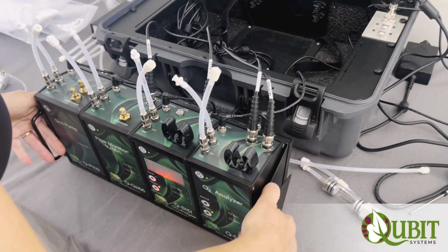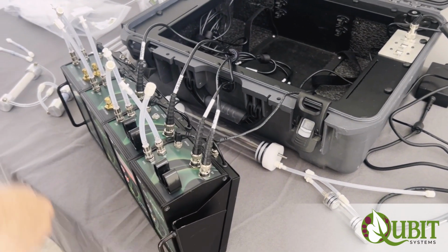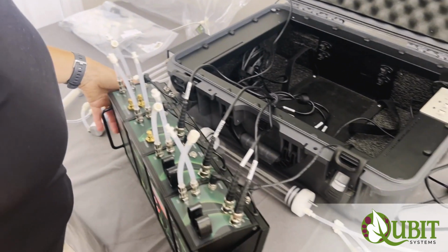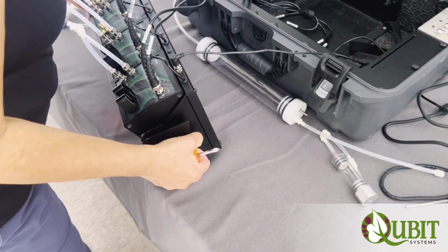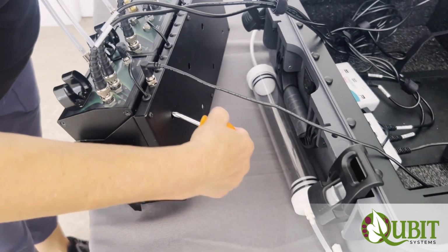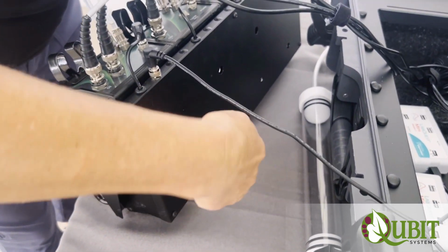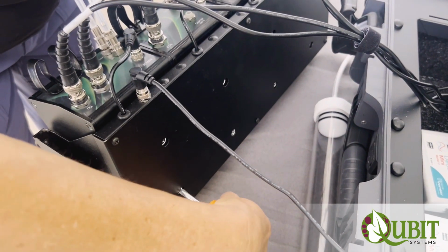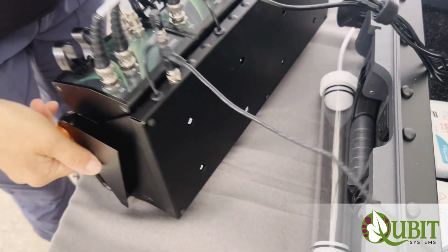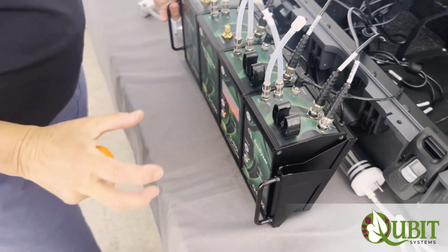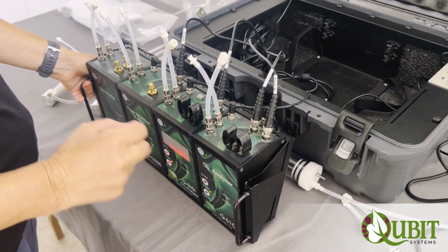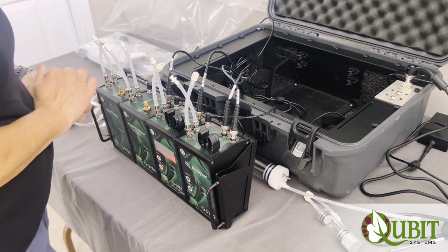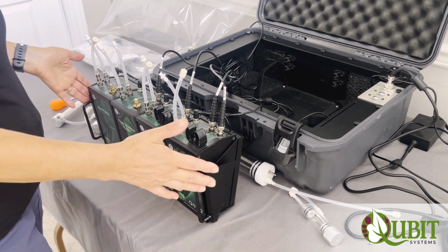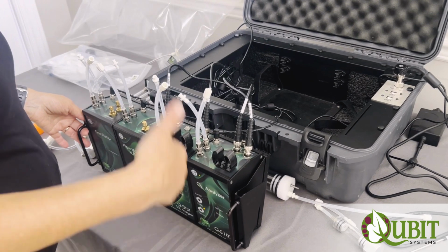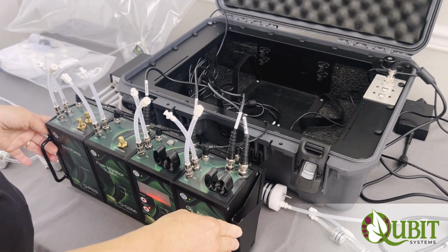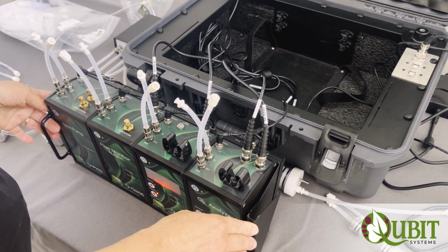To remove any of the components, you need a screwdriver, and there are 2 screws on the back of the sensor tray that have to be loosened up. You have to loosen both of these up. When you do that, each of these components can be taken out, removed, and replaced with another one. If there are any problems with any of the components, they're easily removable. You can send them back to Qubit for any type of service that may be required.